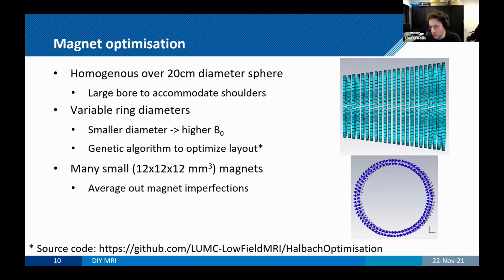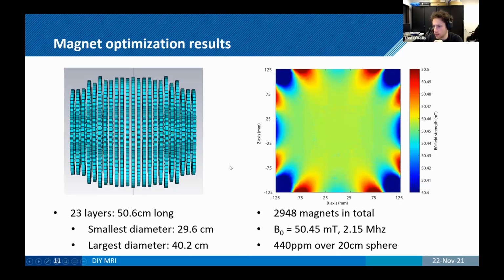So we like that, but then also using so many magnets, because in the end, so I'll show on the next slide, we used about 3,000 magnets. All the little fluctuations between the magnets themselves, because they'll all have slightly different strength and slightly different orientations and things like that, will be averaged out a little bit by the fact that you're using a lot of magnets rather than a few. And then obviously you want the highest B0 field strength you can get, so we just added 2 layers of magnets onto that. So this is the design that we came up with.